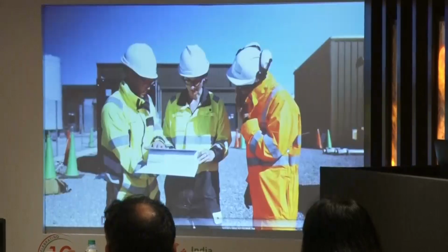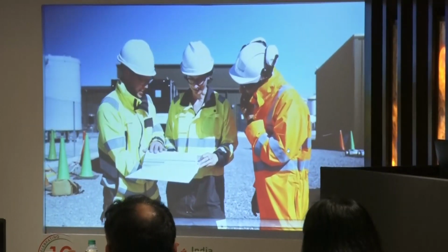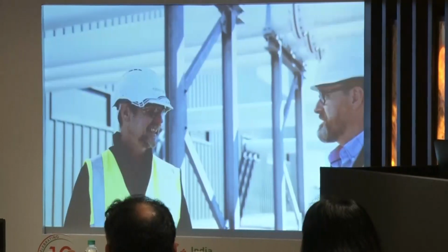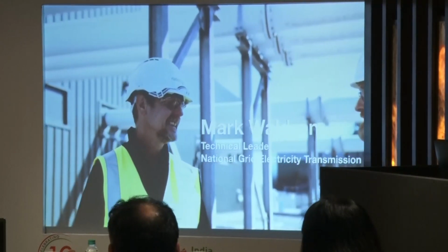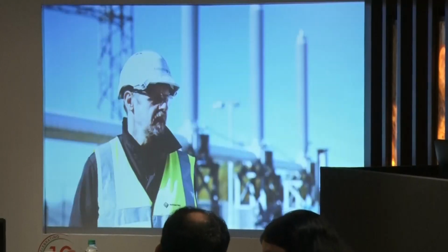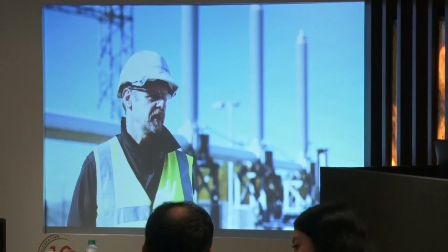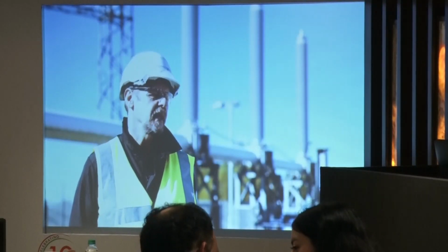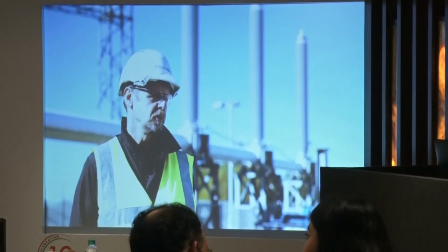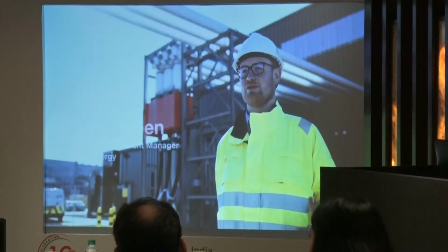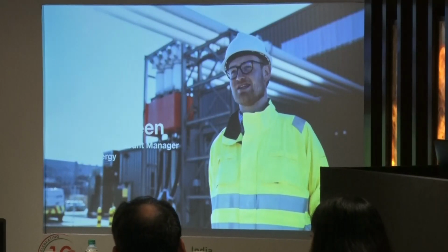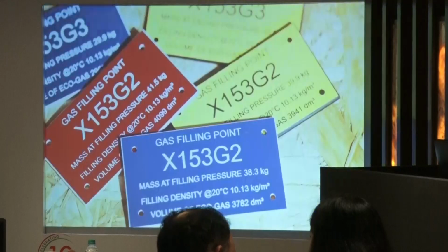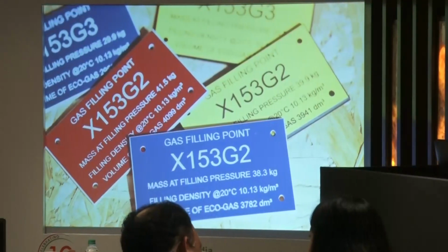Involved in this world-leading project with Hitachi Energy. The project is basically to demonstrate that we can take SF6 from existing equipment, from gas-insulated bus bars, and replace that SF6 with an alternative gas with a much lower global warming potential. The discussion I had with Adrian and the team in Zurich was, wouldn't it be great if you could just suck out the SF6 from these assets and put a different non-SF6 solution in?